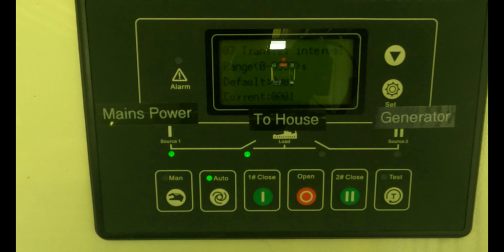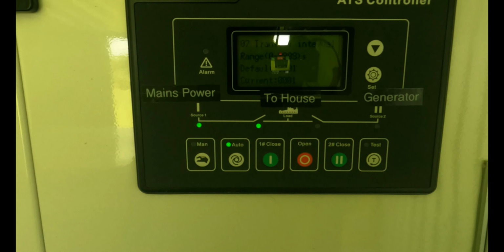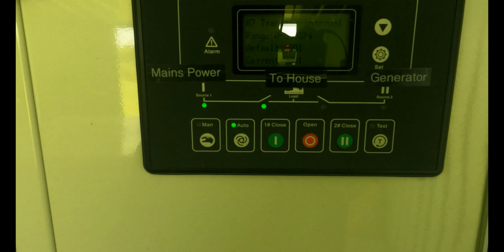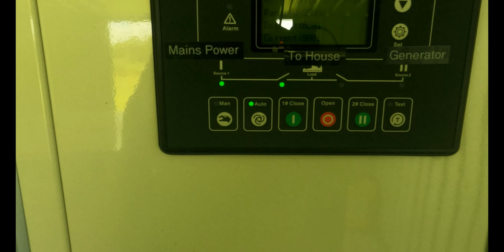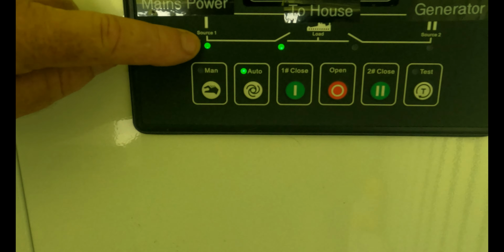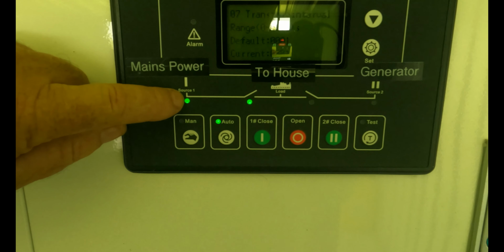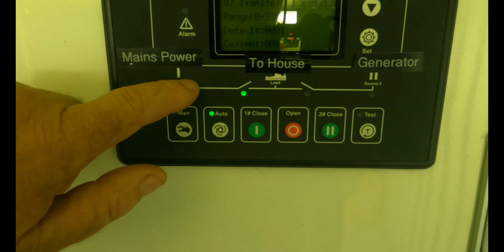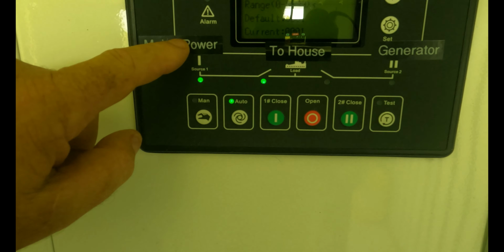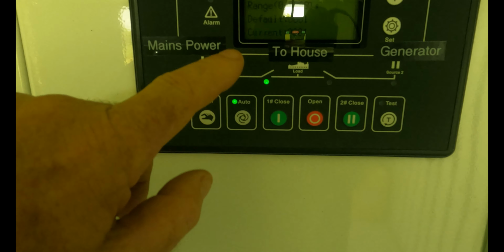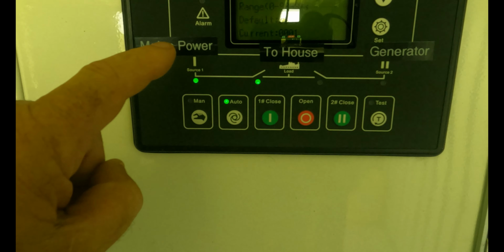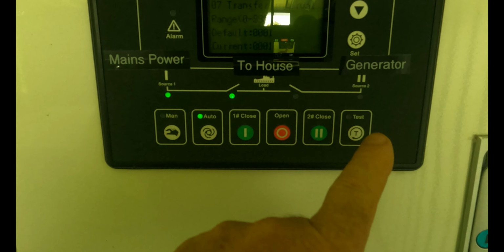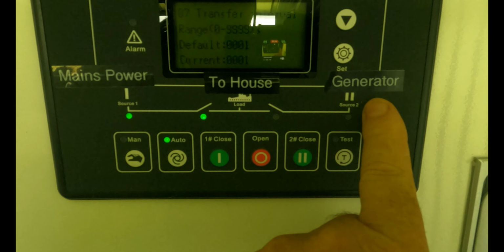This right here is the ATS controller, automatic transfer switch. It's a computer, and what it does is it monitors the main power here, and then it sends it to the house. It does it automatically, and the second the power supply goes off, it'll automatically start up the generator, a second source of power, and then supply it to the house.